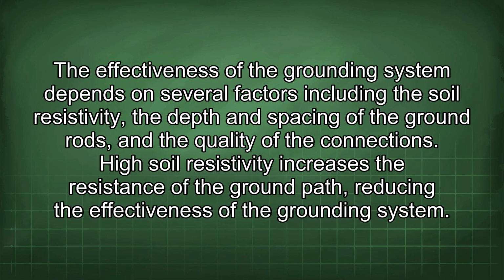The effectiveness of the grounding system depends on several factors including the soil resistivity, the depth and spacing of the ground rods, and the quality of the connections. High soil resistivity increases the resistance of the ground path, reducing the effectiveness of the grounding system.